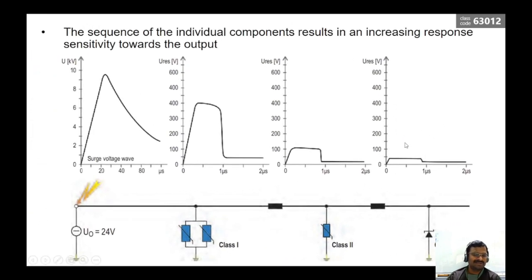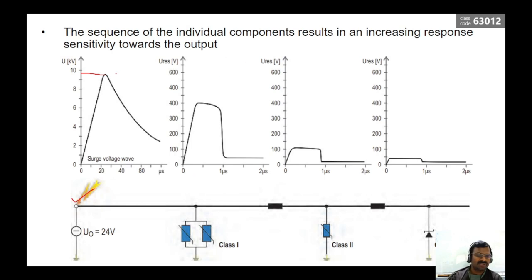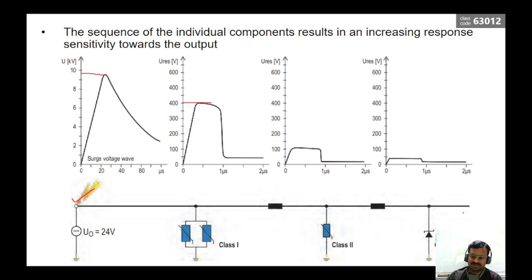You can see in this slide how voltage suppression takes place at different levels of SPDs. The surge is created at the input side at almost 9 to 10 kV. When passing through the type 1 voltage suppressor, it suppresses the voltage from 10 kV to almost 400 V — a drastic suppression. At level 2, it is suppressed further to 100 V. At level 3, it is suppressed almost to the system voltage which it operates at in normal conditions. This is how voltage surge suppression takes place across the different types of surge protective devices.